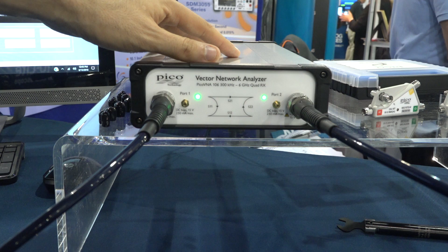And here we have the Pico Technology Vector Network Analyzer. Now, this has some interesting features which I think are worthwhile mentioning. So this is a quad receiver network analyzer, meaning that each of the channels has 2 receivers, which allows them to measure simultaneously the incident and the reflected wave. The advantage of that is that when you want to do full 2-port measurements, you don't have to worry about a switch going back and forth per port, and the switch uncertainties, of course, are very difficult to get out of your S-parameter measurements. And the reason traditionally you don't have quad receivers on instruments of this class is because, of course, of the cost.